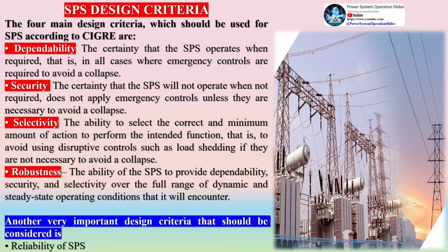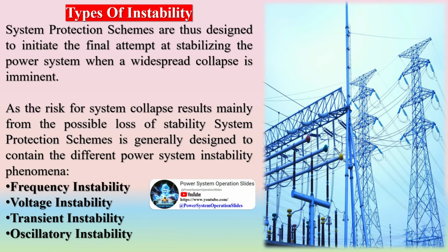It should be noticed that also selected system quantities can be monitored and used to trigger the special protection scheme response, but in contrast to system protection schemes, which will be discussed subsequently, the power system is not necessarily in an emergency state or close to instability, even though there might be a risk to enter the emergency state.